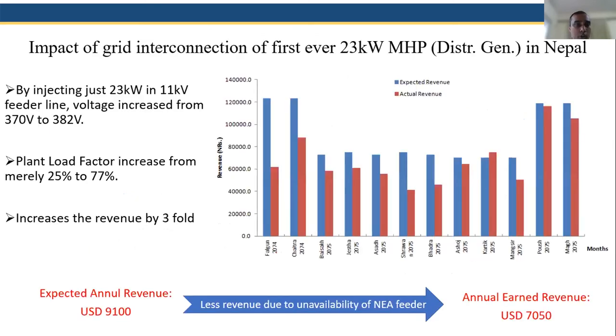This is the first micro hydro system we interconnected into the grid. You can see the impact from the grid perspective. Before interconnecting the micro hydro, the voltage of the grid was 370 volt. Just after interconnection, this increased to 382 volt. So you can see the voltage improvement because of the power injection at the distribution level from the interconnection of micro hydro.